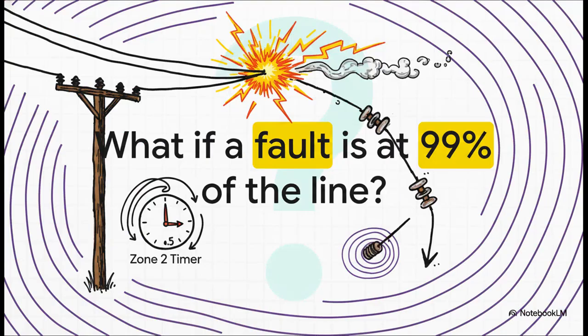The thing is, polite and disciplined isn't always good enough. As grids got larger and a lot more heavily loaded, engineers realized this strict zone system had some terrifying flaws. For instance, what happens if a catastrophic short circuit hits at exactly 99% of the transmission line? That's right in that 15% blind spot we purposely left for Zone 1. That means the local relay has to just sit there and wait for its Zone 2 timer to run out. Sitting around for half a second while a massive fault rips through the grid is just too slow. Equipment melts, lines drop, instability ripples out everywhere.